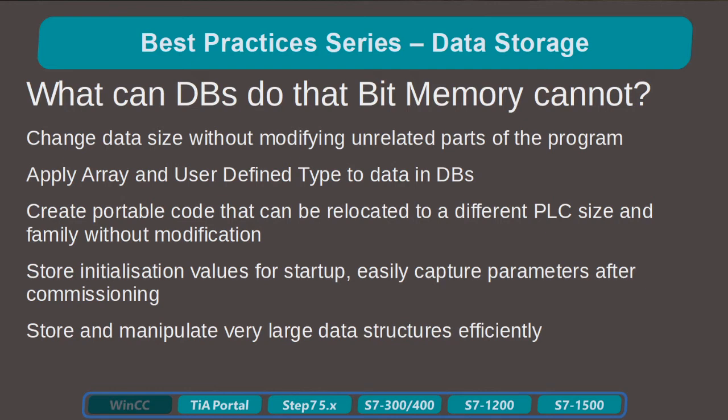Another good reason is you can create portable code, where the DB goes with the FCs and the FBs to take that function to another PLC, either for a similar task or for a different task. So we can tie the program's operation with the data that it operates on and port that from PLC to PLC with minimal change, usually not any change.